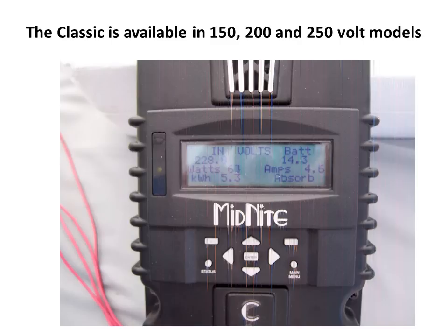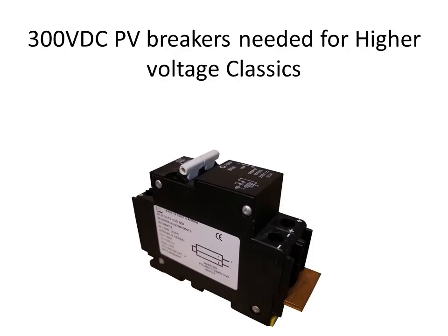The Classic is available in several models with input voltages of 150, 200, and 250, and charges up to a 120 volt nominal battery bank. Operating above the 150 volt rating of standard controllers — this picture shows an operating voltage of 228.8 volts DC — brings up the need for high voltage breakers on the PV side. MidNite has breakers rated for 300 volts DC in DIN rail mount as well as panel mount. It is important to use DC rated breakers rated for the voltage they'll be working at. We recommend our 300 volt versions of our MNE-DC or MNE-PV breakers for the input of the Classic 200 or 250.